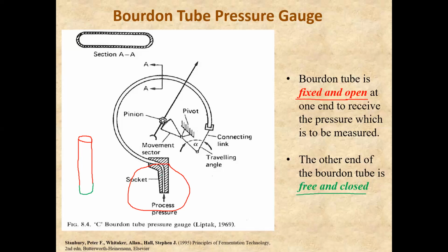which was this end, this was open and it was also fixed. The bottom of the test tube is closed. This is the reason when you add liquid, the liquid is retained in the tube. So the other end of the tube is closed so that it can retain the liquid. If it was not closed, the liquid would have spilled or come down. So the other end of the Bourdon tube is closed, which is this end. This end of the Bourdon tube is closed, but the end which is closed is also free. That means it can move.